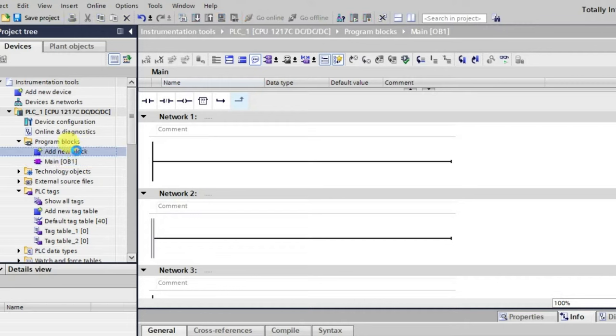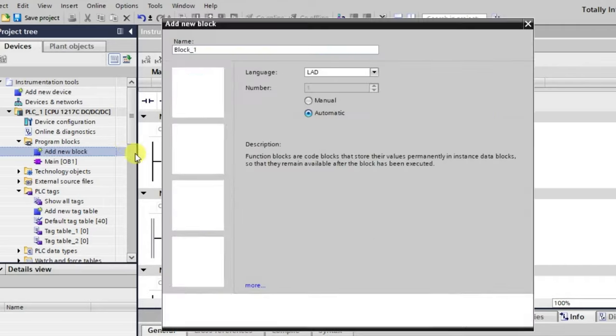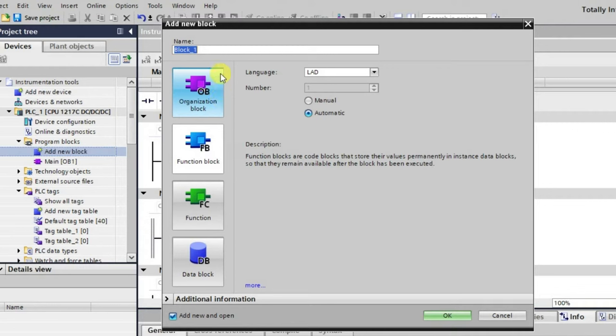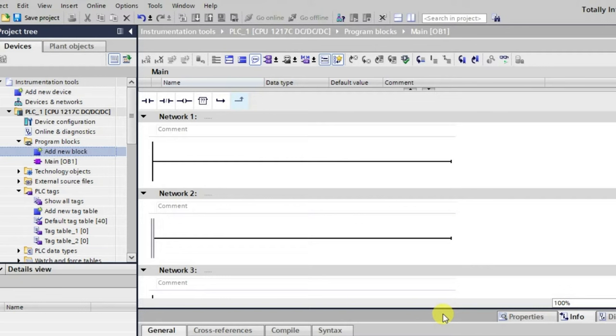If you double-click you'll be able to observe that we have multiple options to create function blocks. This is our main organization block, this is our function block, then function, and this is the DB. The DB is basically used to store all the content of any function block, timer, or counter. The main organization block is where the program executes, and we'll be calling functions in this main organization block.